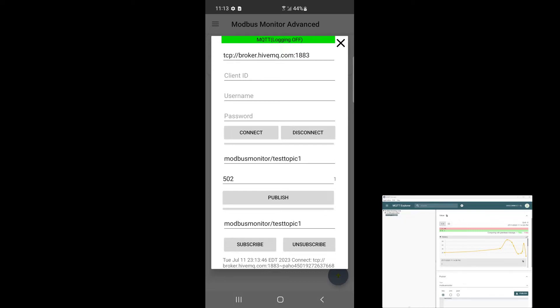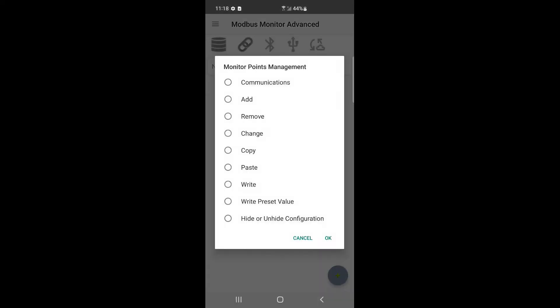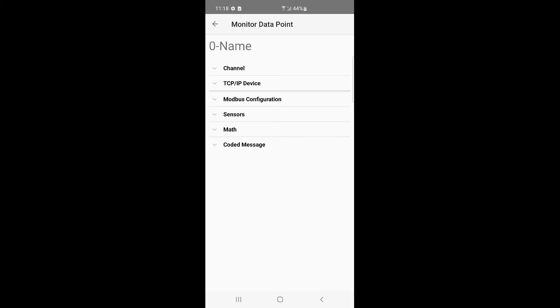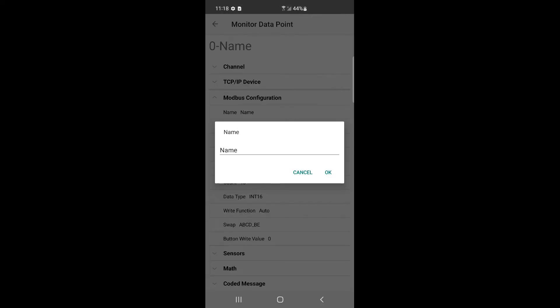Now let's try to publish data automatically by configuring a monitoring point. Click on the monitoring point and then click change. Configure the TCP IP channel and set the IP address and port of the remote Modbus server. Set the name similar to MQTT's topic and subtopic.